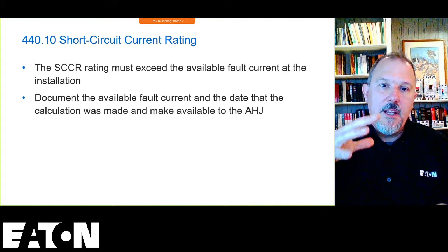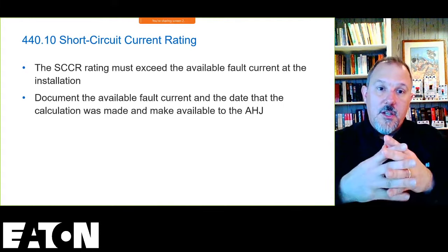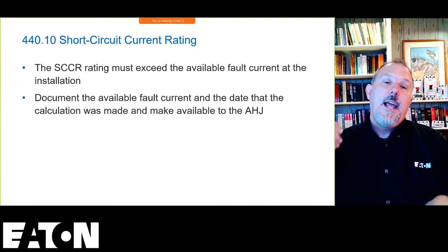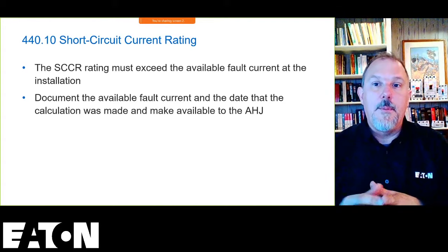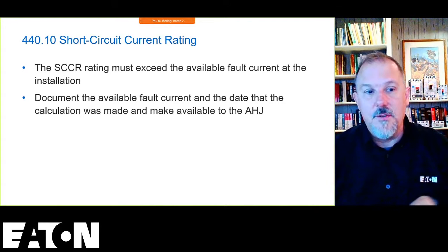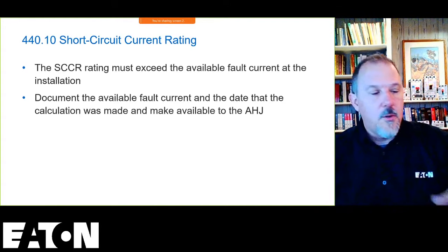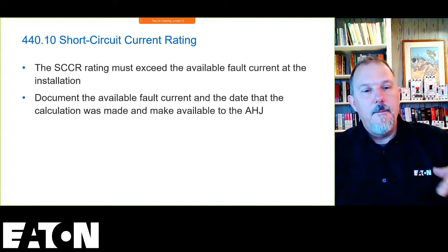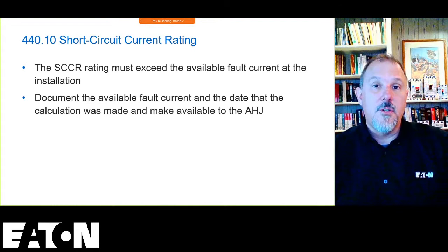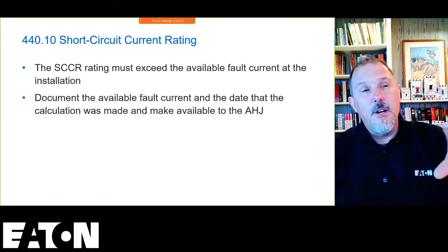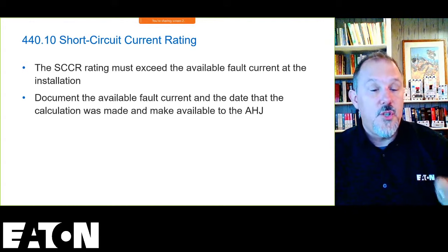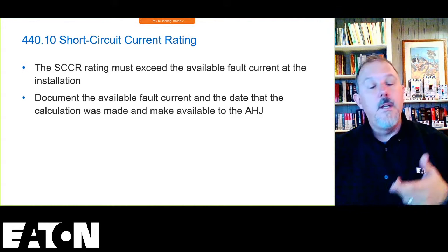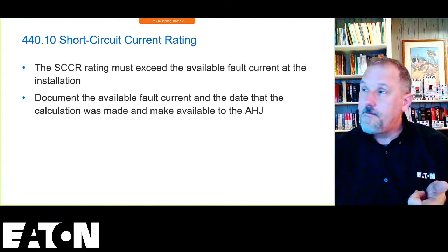So I'm going to have to document my available short circuit current, and I'm going to have to mark it with its short circuit current rating, and someone has to do that comparison, and it's probably going to be an electrical inspector. But that's just a new requirement in the 17 cycle that required the calculation of that fault current and providing it. It's not required to be marked, but it is required to be documented and made available to the authority having jurisdiction.